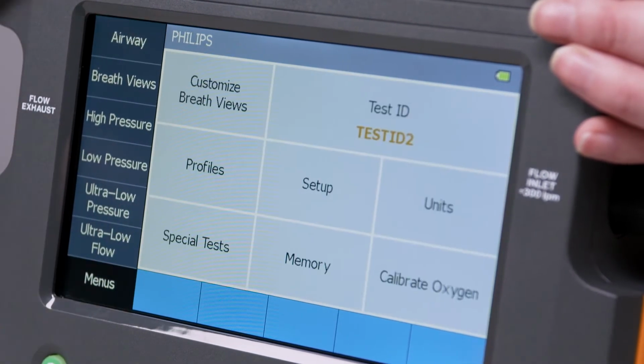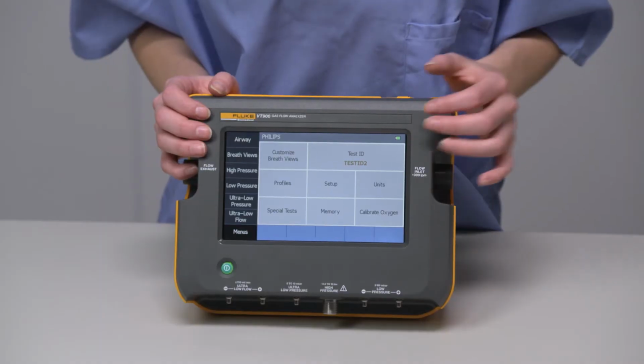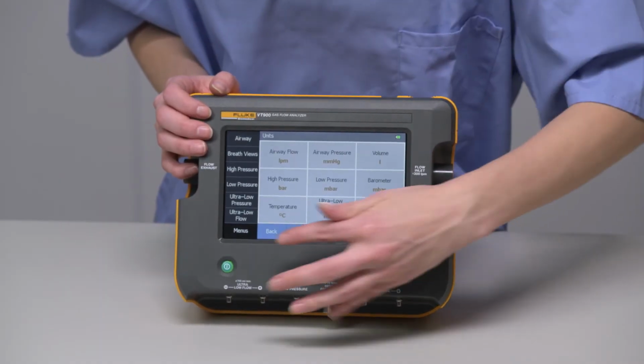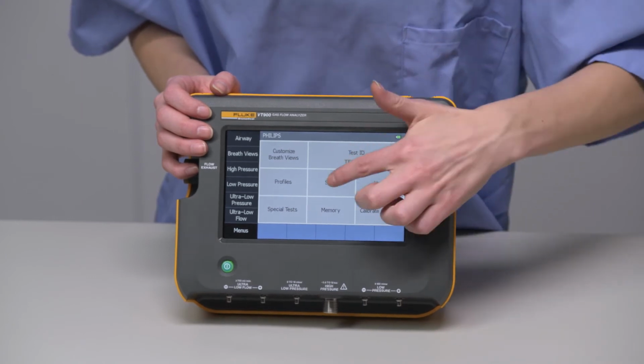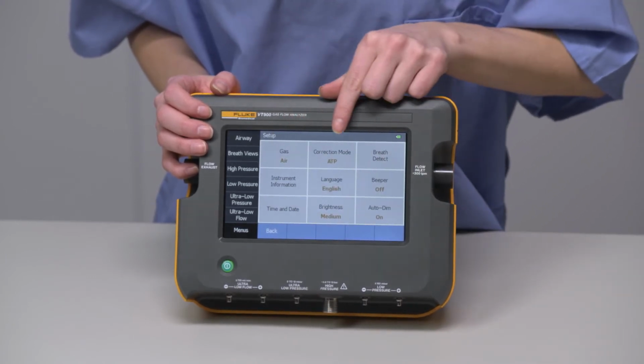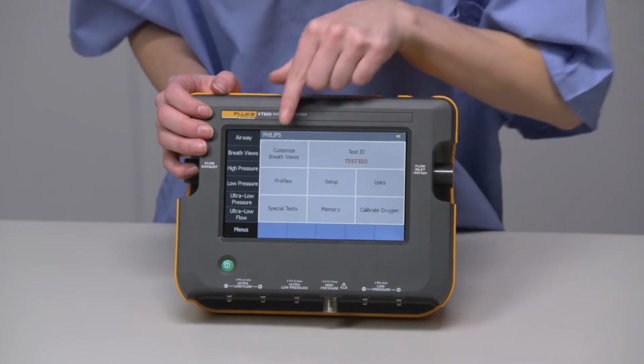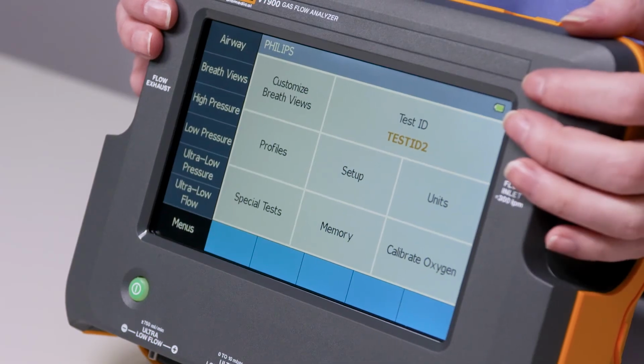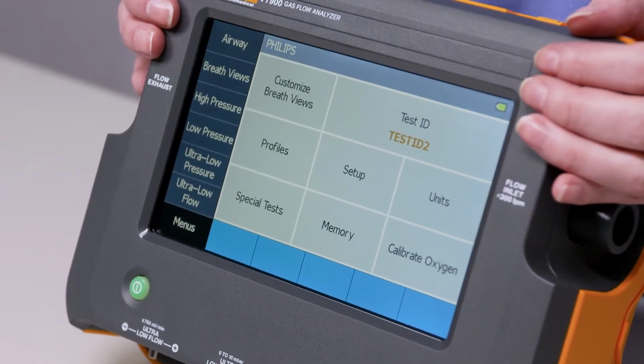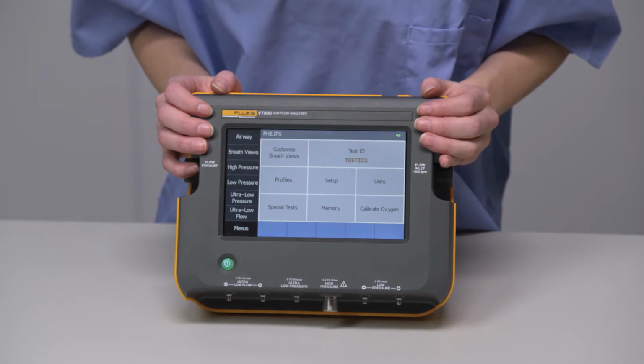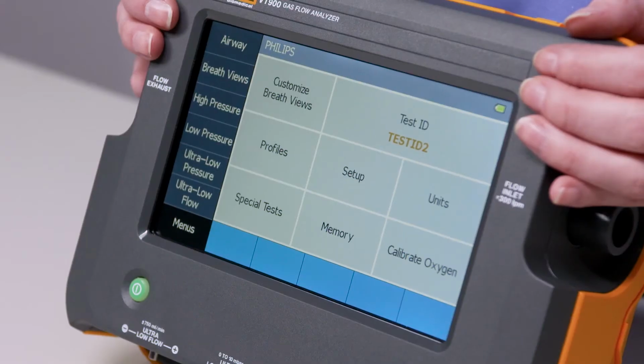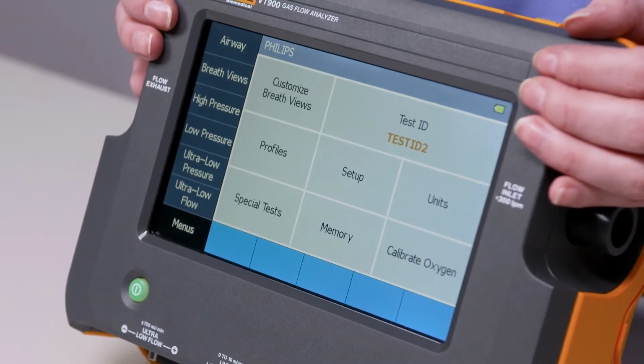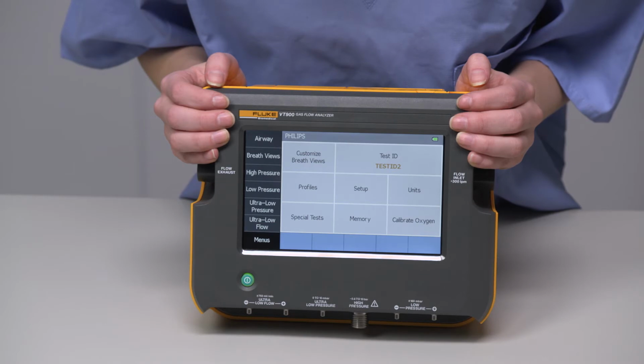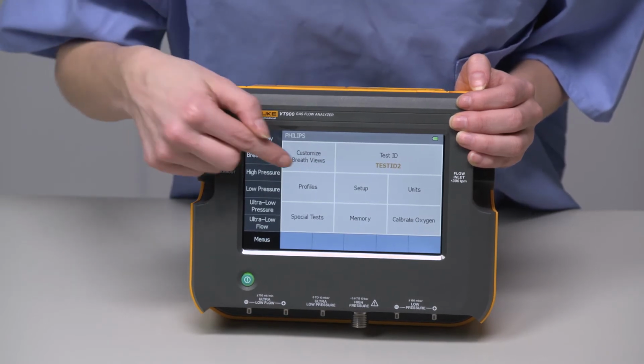Now we can configure the whole device in this way: units, gas type, correction mode, breath views, or other settings. You can configure to personal preference, or sometimes manufacturer service manuals have measurements in a specific unit, and it's helpful not to have to do manual conversion. When we have the device set up the way we need for our model or type of testing, we can now save it as a profile.